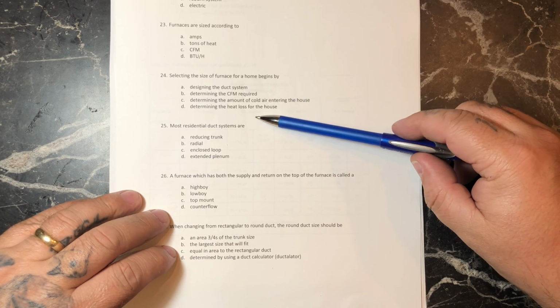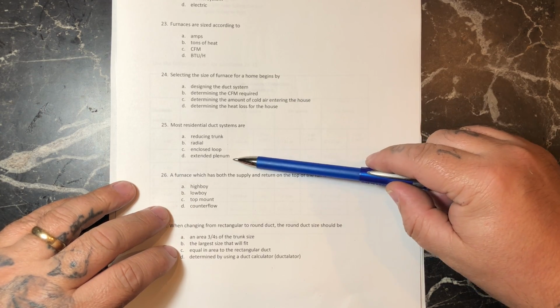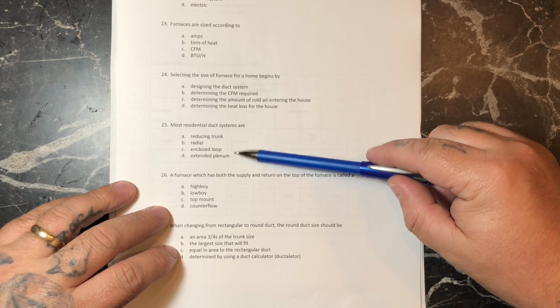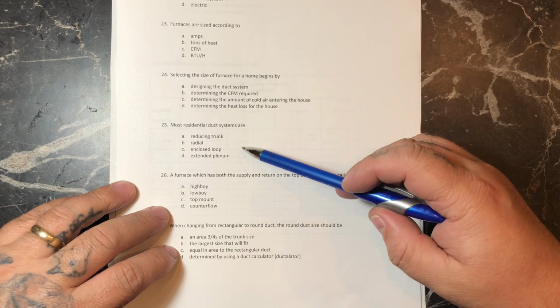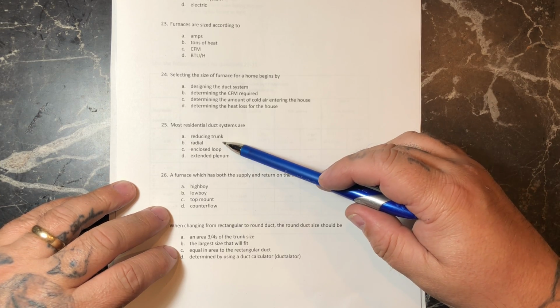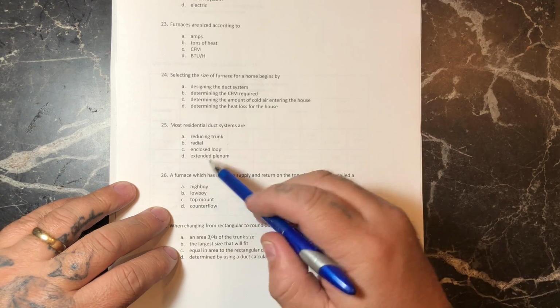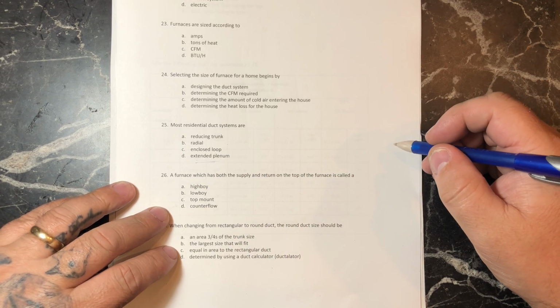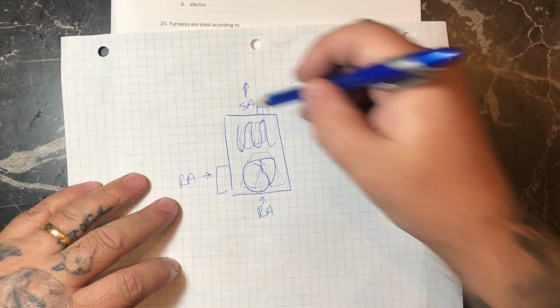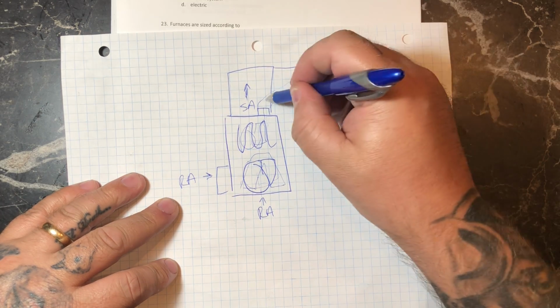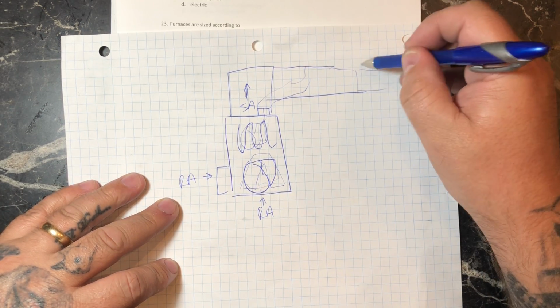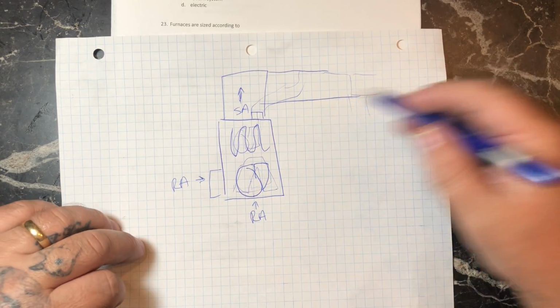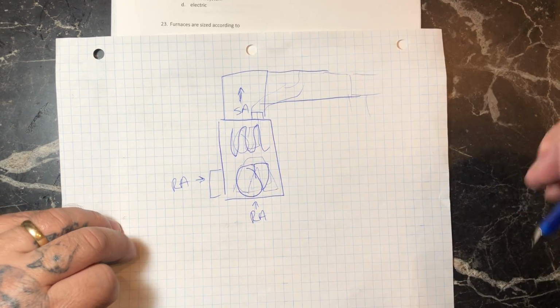Most residential systems are extended plenum. I think on the very first video I showed you guys this typical extended plenum. There are these other ones like reducing trunk, radial, and enclosed loop, but extended plenum is the right one on that one. That's just where the furnace has a supply plenum, and then it has the main branch that comes off and feeds all the different rooms. So that's a plenum, and the ductwork that comes off it is technically an extended plenum.